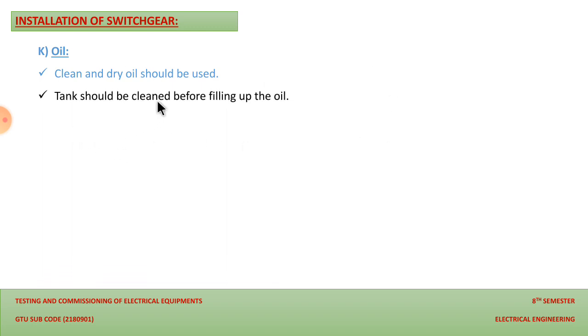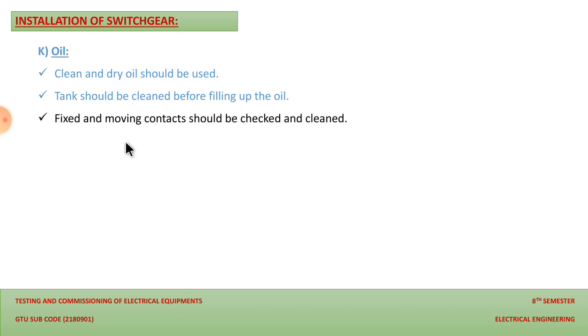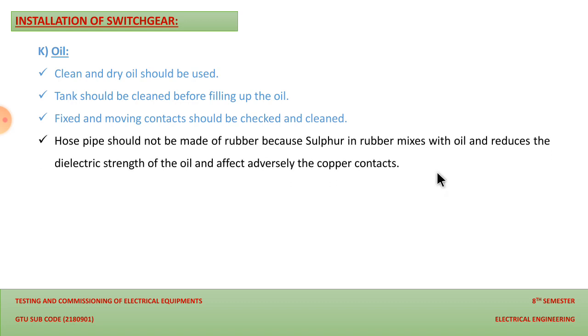Then the tank should be clean before filling up the oil, because if there are dust particles inside the tank, that will become dangerous for the operation of the switch gear. So we need to clean the pit where we are filling the oil before we fill the oil inside the tank. Then fixed and moving contacts should be checked and cleaned. So yes, check whether there is corrosion or not. And we need to perform certain tests of the moving mechanism of the switch gear, that we have to ensure before we install the device.